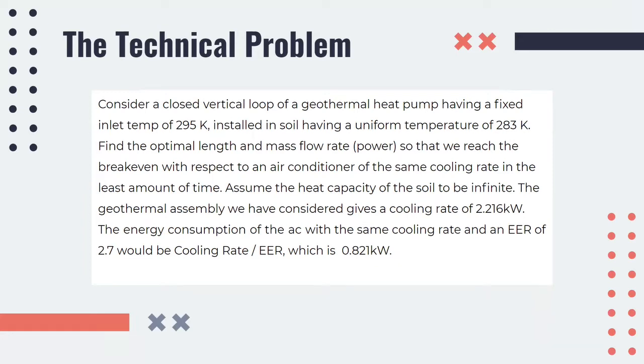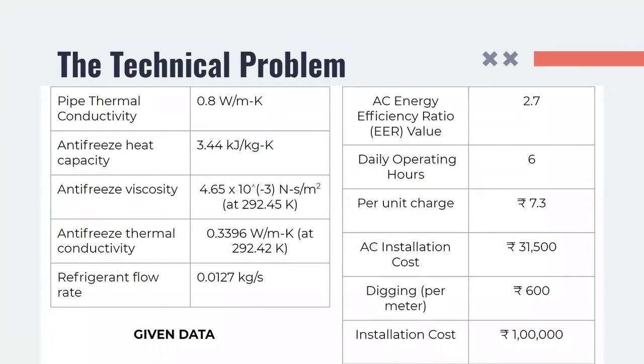The geothermal assembly we have considered gives a cooling rate of 2.216 kW. The energy consumption of the AC with the same cooling rate having an EER of 2.7 would be 0.821 kW. We use the following values in the calculation: the pipe thermal conductivity, the antifreeze heat capacity, the antifreeze viscosity, the antifreeze thermal conductivity, refrigerant flow rate, AC energy efficient ratio value, daily operating hours per unit charge, AC installation cost, digging cost per meter and the installation cost. Now, handing over to Devishree.